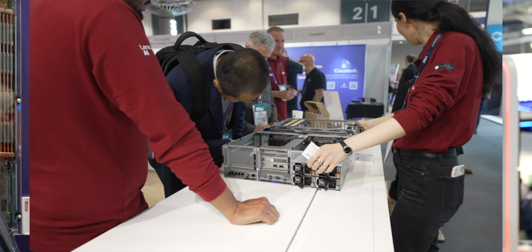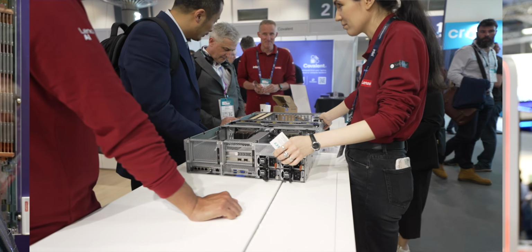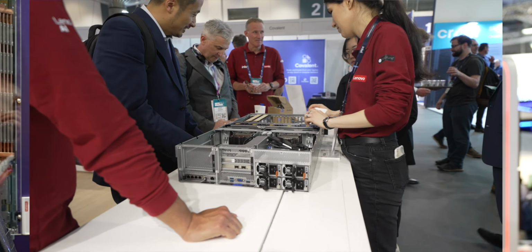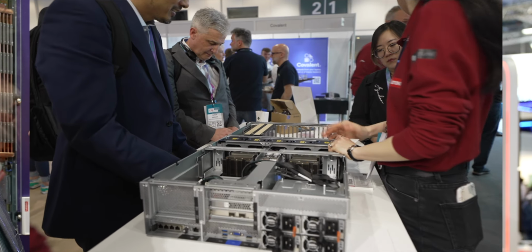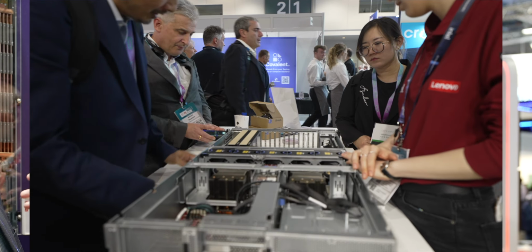Based on that, we determine what type of CDU is needed and what the flow rate should be for the water. Again, this is water flowing through it—not a glycol mixture. It's demineralized water, and we're the only ones using demineralized, non-toxic liquid in our closed ecosystem.